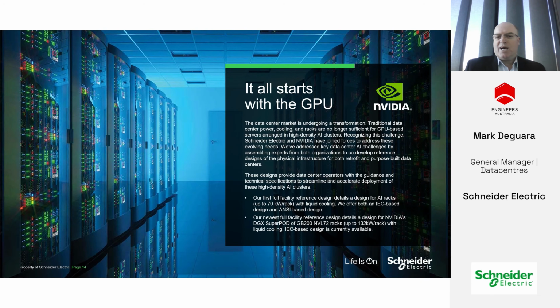So, where does it all start? It starts with the GPU. If I look today, or actually, if I look back, we used to sort of build from the outside in. We used to go, okay, we're going to build a 5 megawatt data center or a 1 megawatt data center. And we go, yes, we need MV, we need transformers, we need MV switchgear, we need UPSs, etc. And we were going, okay, well, we'll have 1 or 2 kilowatts a rack, and we'll design for that. It's actually flipped. So today, it's very much starting with the GPU.